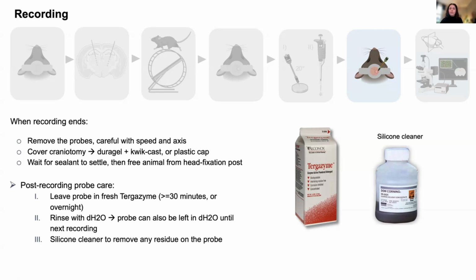Then you take care of the probe. You generally leave the probe in a solution that will degrade any tissue remains that are stuck to the shank. So you can use tergazyme, and you should then rinse it with water. You can also leave it in water until your next recording. That's also fine. For anything that's stuck to the probe, like any residue that has not come off, you can use a silicone cleaner like the one that I put on the screen. That also works really well, and it provides some extra help in keeping the probe clean.